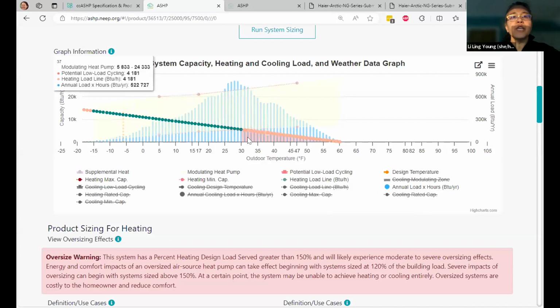What's happening over here, where the slope is a different color, is that the load of this space—I keep calling it a building, but it's really a space in a building—is too low for the minimum capacity of this heat pump. So the heat pump isn't going to modulate to meet that load.